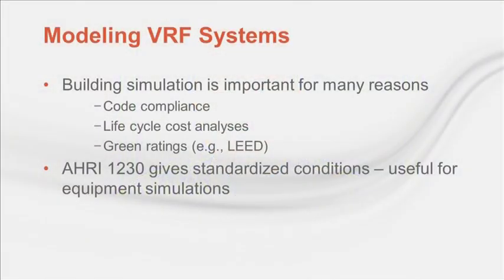Today, building simulation is used to show compliance with industry building standards and codes, make system comparisons, and for green ratings. While variable refrigerant flow systems have existed since the 1980s, VRF energy simulation has continued to evolve. Prior to the introduction of the standardized performance rating method in AHRI 1230, design and rating conditions for VRF equipment varied. This could pose a problem for simulation programs if extrapolation was needed to operate equipment beyond the provided rating conditions. So here's our building again.